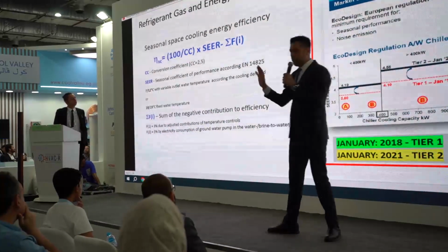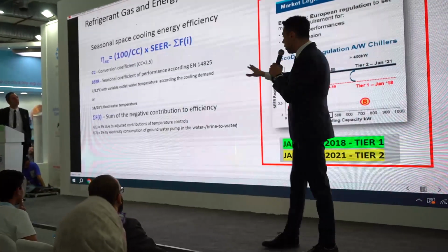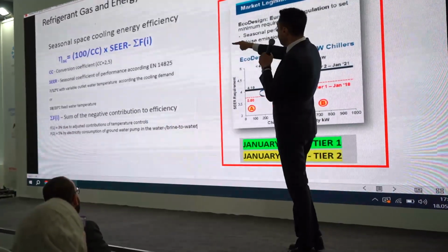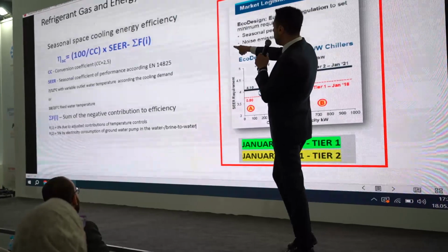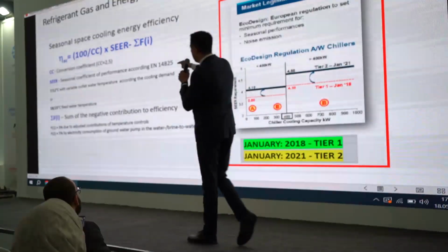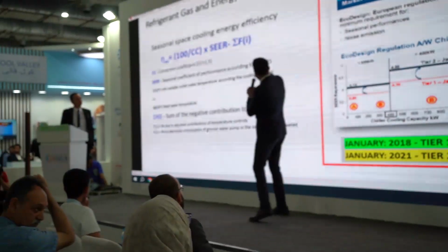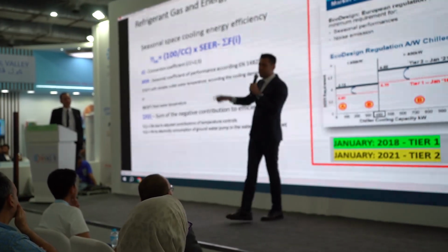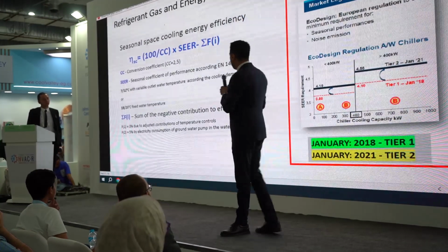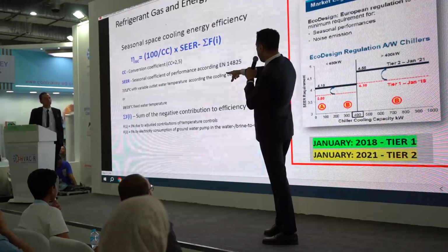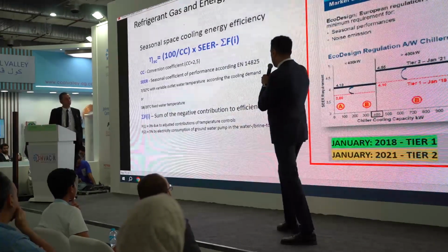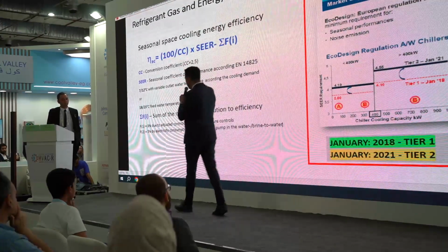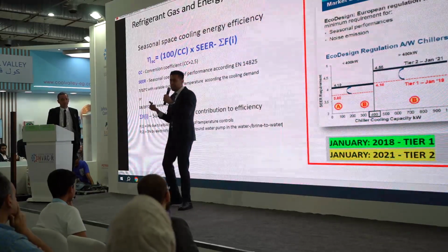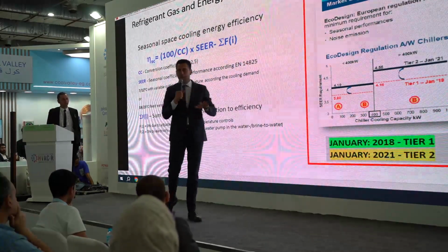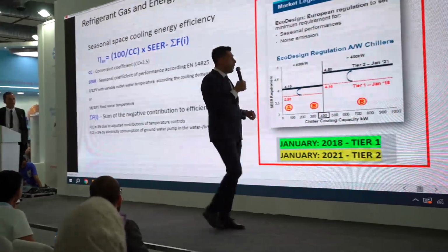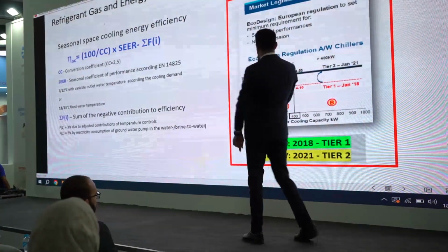Simply the calculation, I'm not going to go into the detail, but it is a very simple calculation, you can find it everywhere actually. The conversion factor, seasonal energy efficiency rate based on EN 14825. This number you never forget. You will be seeing this number again and again in the catalogs. And of course, there is a calculation where some negative contribution, for example, 3% due to the adjusted quality of the sensors, time response problems or any other kinds of problems, is going to affect and reduce the total seasonal energy efficiency.